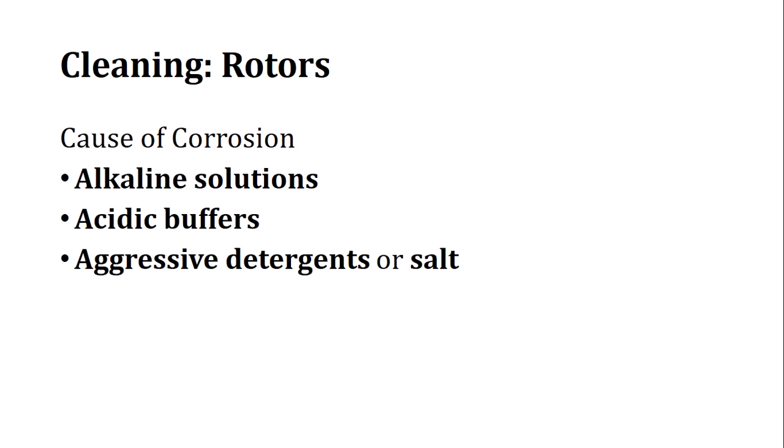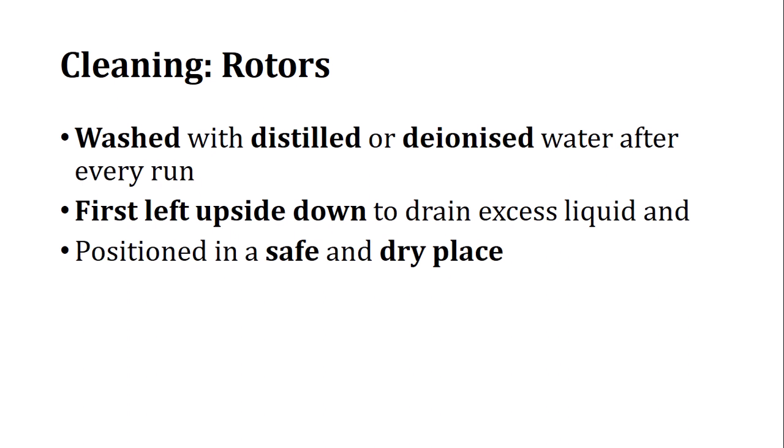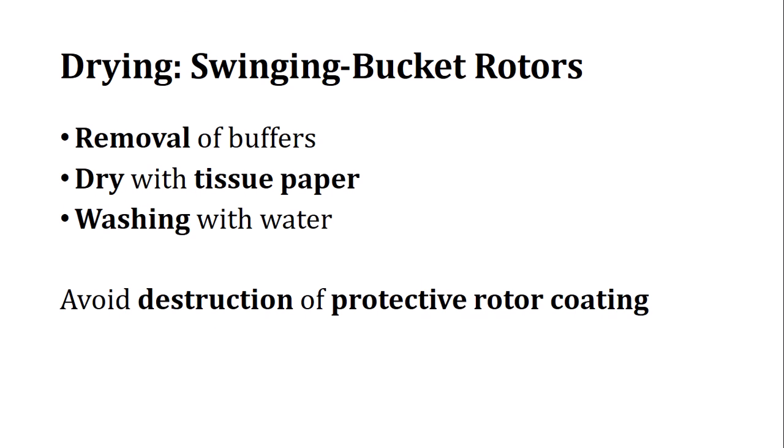Alkaline solutions, acidic buffers, aggressive detergents, or salts that may cause corrosion should be avoided, and if contact occurs, they should be removed immediately. The rotor should be washed with distilled or deionized water afterward. It should first be left upside down to drain excess liquid, then positioned in a safe, dry place with no humidity. For swinging bucket rotors, remove any buffer, dry with tissue paper, and wash with water. Always avoid destroying the protective coating layers.